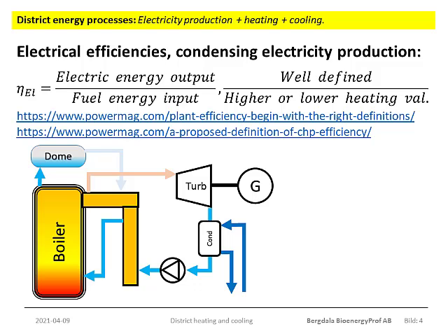Now just to go through the simplest process. Based on the lower heating value, most coal-fired condensing electricity production will exhibit an electricity efficiency of about 40 to 45%, or at the very least below 50%. The remaining part, more than half of the fuel energy, is cooled away to the sea, to a river, or in a cooling tower. The very simplest schematic for a condensing power station is what you see in this slide. And I will just point out the most important features of it.